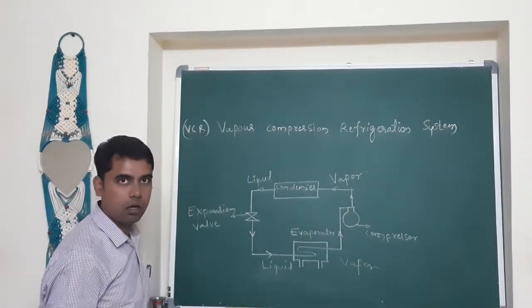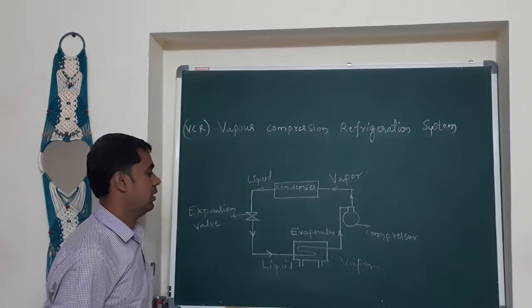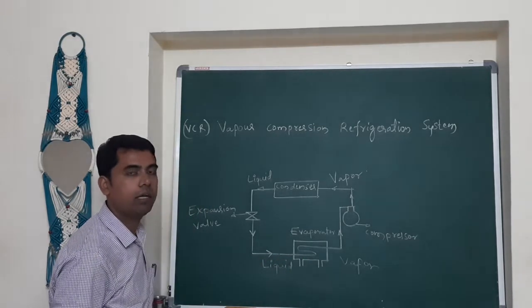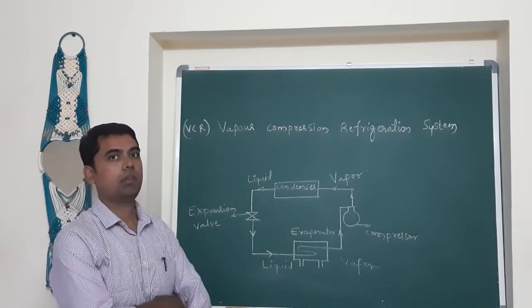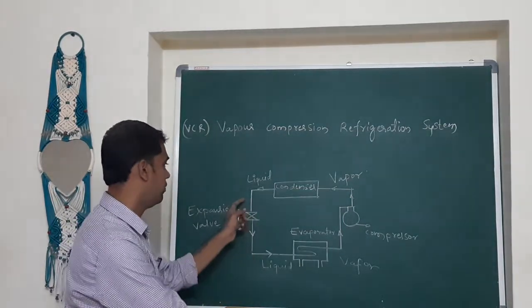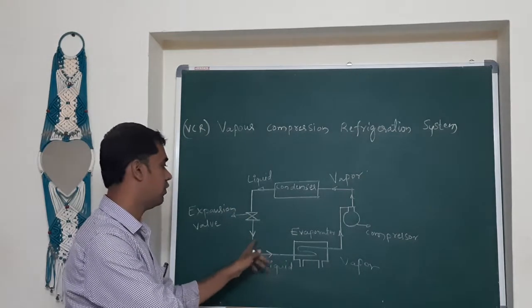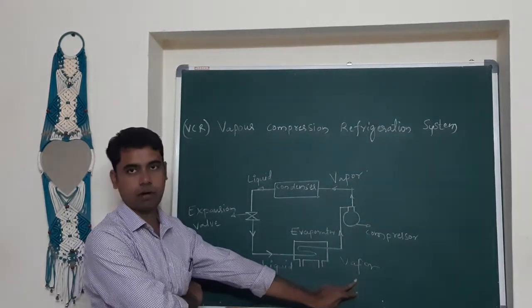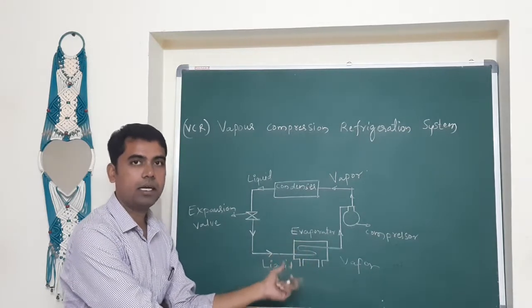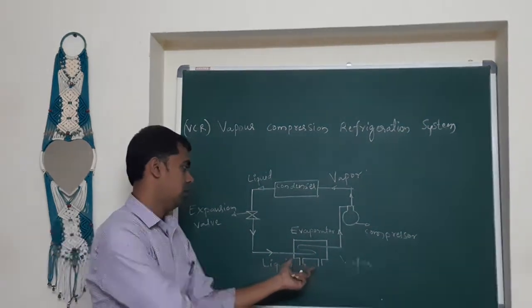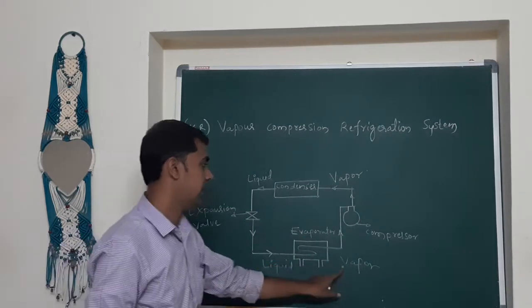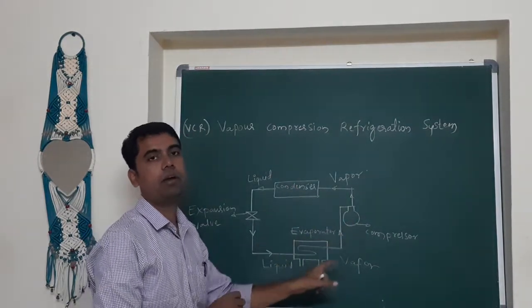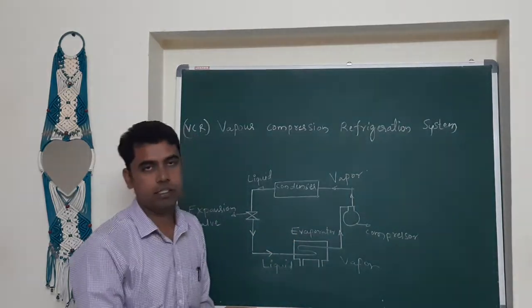As the refrigerant enters the evaporator, it will be a low pressure liquid after passing through the expansion valve, where its pressure is reduced. Inside the evaporator, which is located within the space to be cooled, the refrigerant evaporates and forms vapor, absorbing latent heat of vaporization.